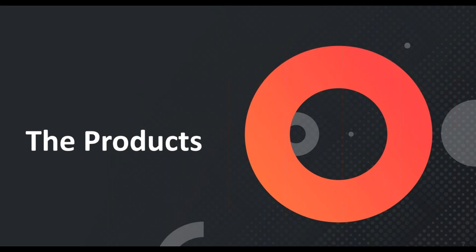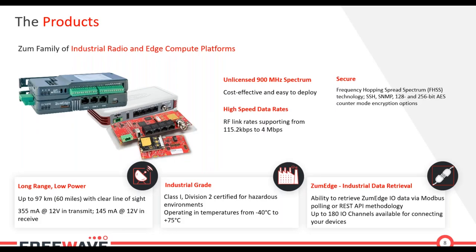Getting into the products themselves: the Zum family is FreeWave's current industrial radio and it has a number of form factors — an OEM board-level radio, a full-size board-level radio, enclosed radios, and a DIN rail mountable IO solution. The entire Zum family operates at 900 MHz — specifically 902 to 928 MHz in the US and Canada — which allows you to power up a system without obtaining a license. Output power is limited to one watt, but even with one watt you can accomplish miles of data connectivity.